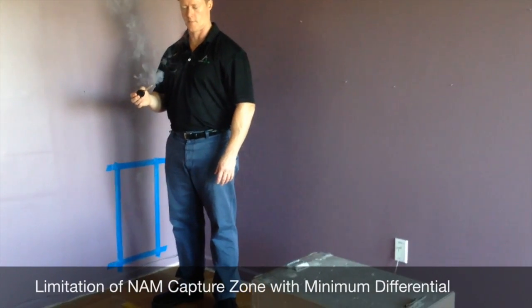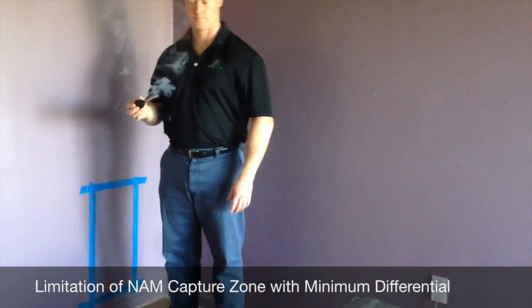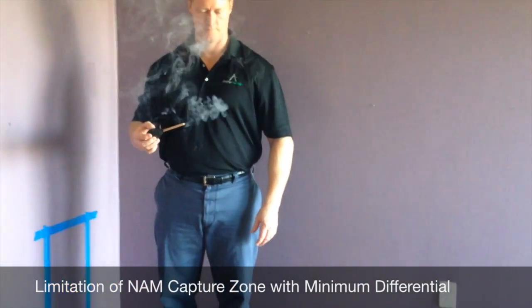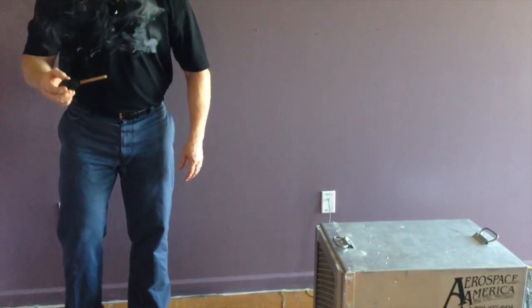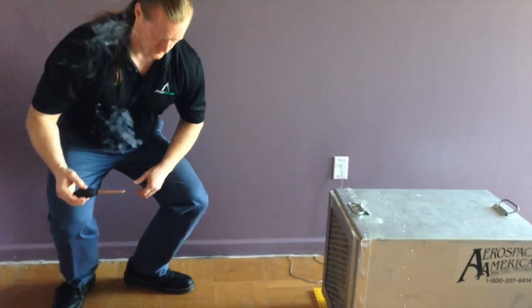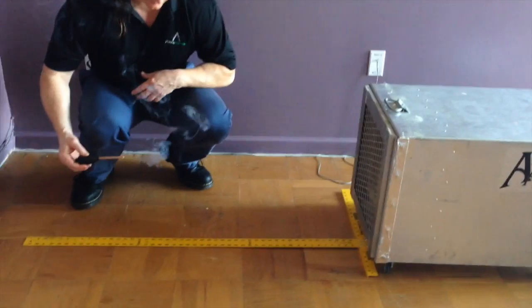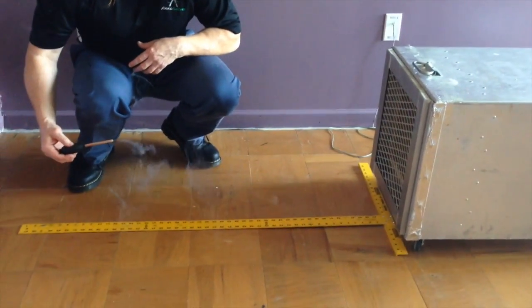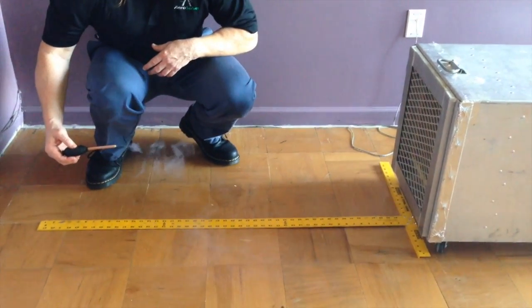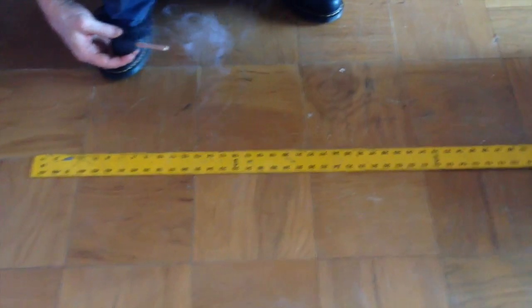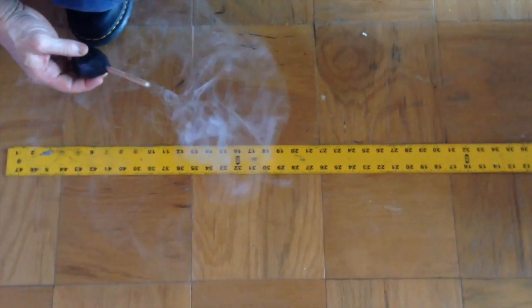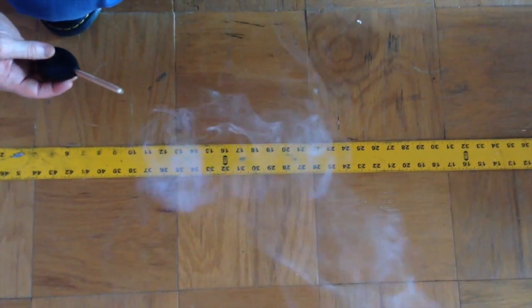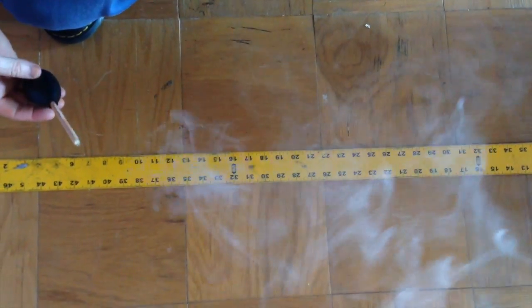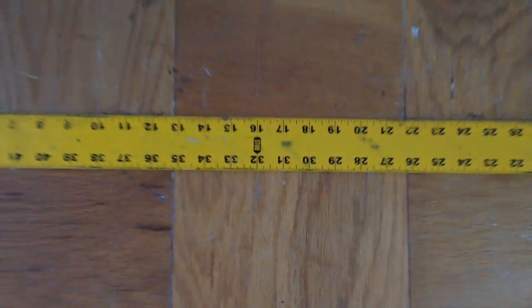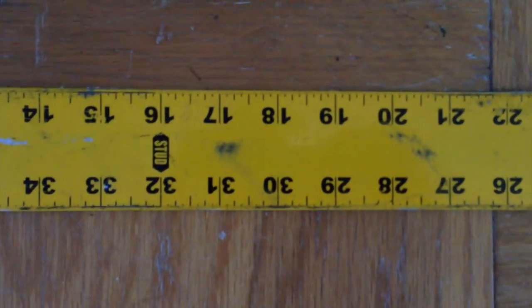Negative pressure differentials do not expand the capture zone of negative air machines. This video shows why negative air pressure differential containments don't really clean the air. The IICRC S520 standard for mold remediation and various guidelines from New York City to the US EPA suggest this practice should be used, or may be the most common method used.